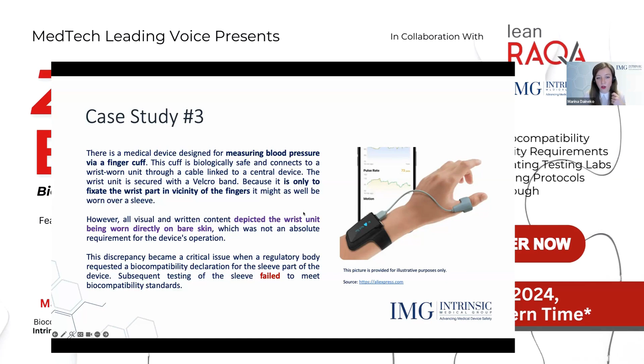And because it's only to fixate the wrist part in the vicinity of the fingers, it might as well be worn over a sleeve. But all the documentation, like the instructions for use and all the marketing information, had a picture of the wrist unit being worn directly on bare skin. And the Notified Body noticed it, and they asked about the biological evaluation of this part. Unfortunately, the tests that were performed to provide evidence that this wrist unit is biologically safe failed. It was not considered, it was not even intended, but all the information, marketing information, instructions for use, etc., had this picture showing that this wrist unit can be used on bare skin. And here we have contact with intact skin, right?